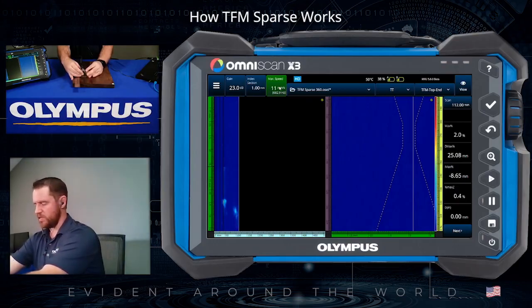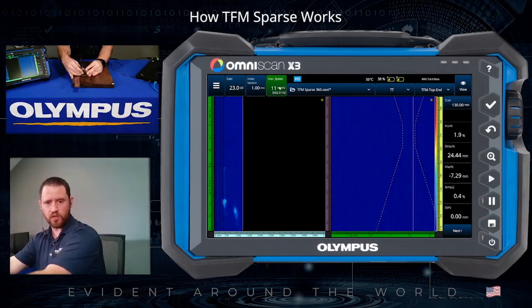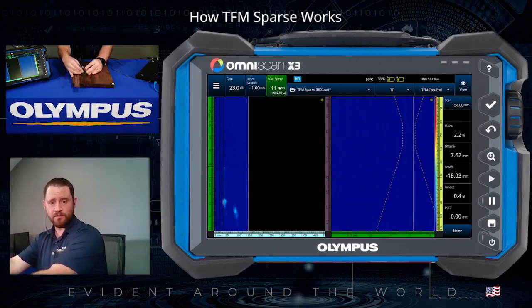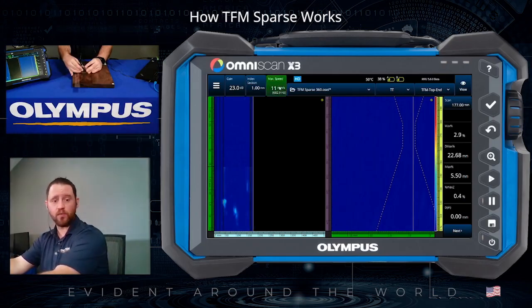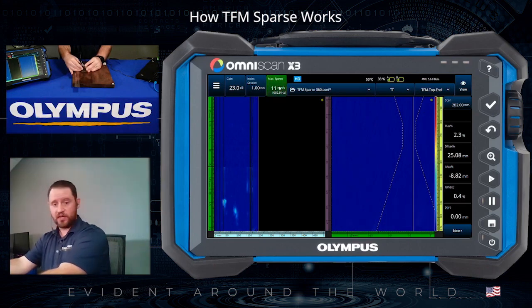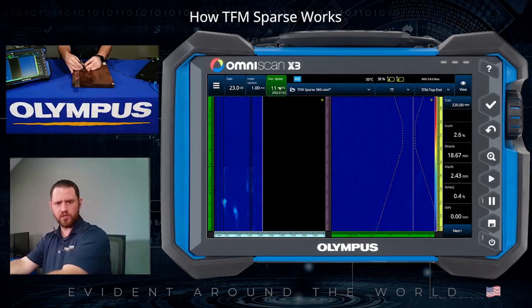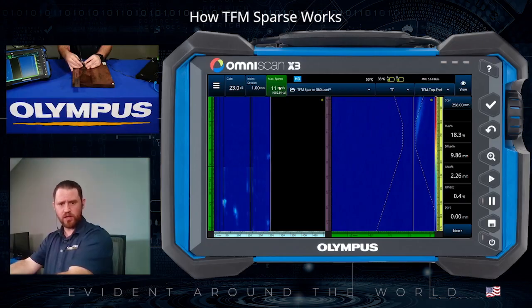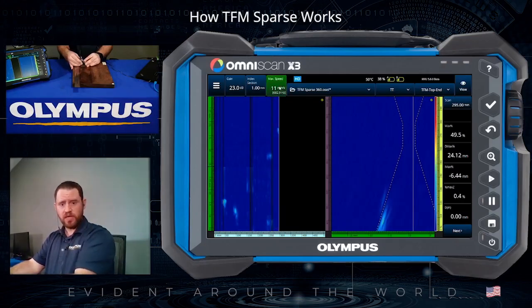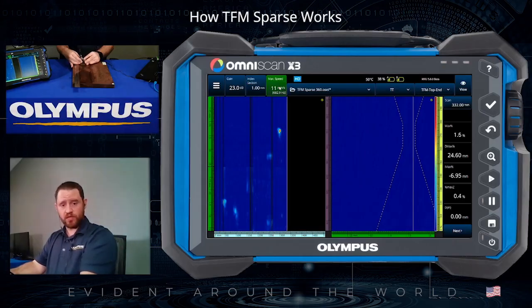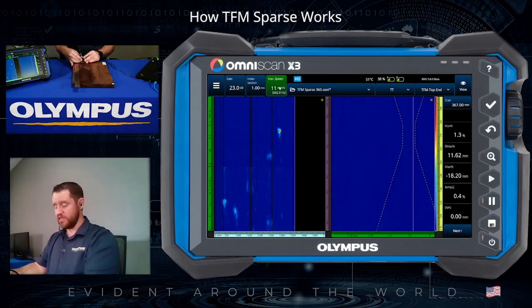And that makes it a little bit difficult to pull the transducer without missing lines of data. As I pull here, if I move too quickly, you can see that that green light flashes red, indicating that I've missed data during this data collection. And you'll also notice on the two top views on the left-hand side of the screen, there start to appear black lines of missing data. So I've got two issues here with this particular setup in running the full FMC data collection. And that is my slow scan speed. So you can see here just how slow it takes me to run the acquisition. And then the propensity to miss data lines.